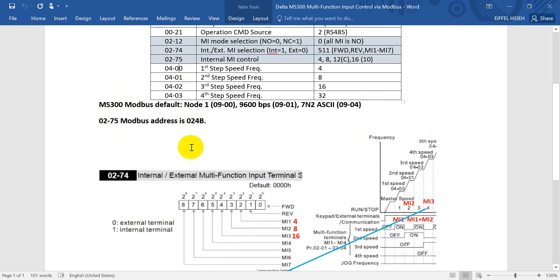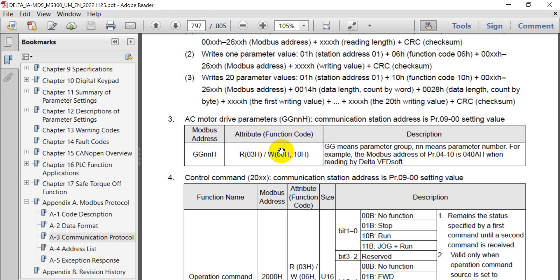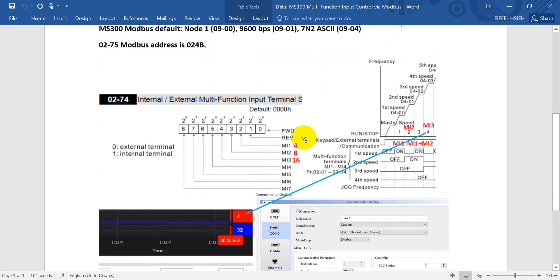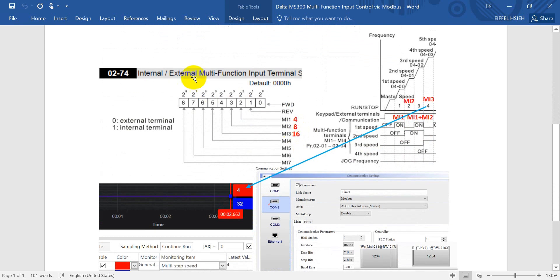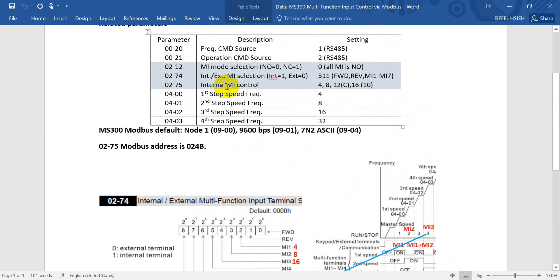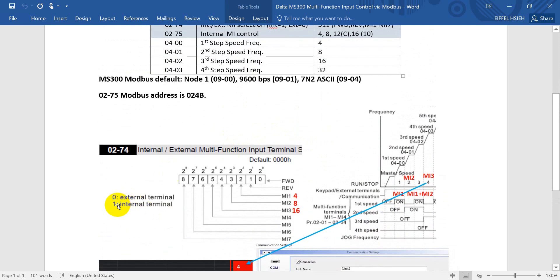As I mentioned, we can enable the function through P02-75. The Modbus address of this one is 024B. If you don't know the definition, you can check our user manual. It mentions how to calculate. Example: P04-10 will convert to 040A. This already mentioned earlier we have to define the internal or external. Internal means we use Modbus controlling, external uses physical wiring.